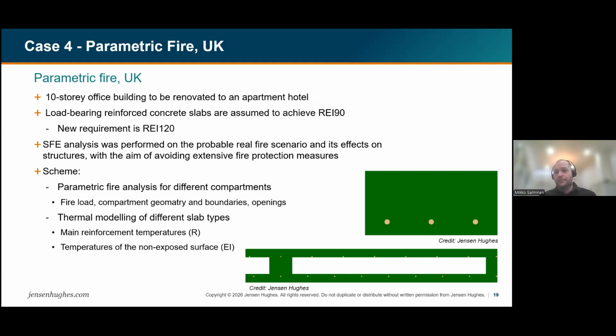And parametric fire works really well in small compartments where you can assume that the temperature distribution is more or less uniform in the compartment. It doesn't really work well if you have a fully open office area, because then you may have a traveling fire moving all around in the floor. But in small compartments, like in this case, the parametric fire curve gives a relatively good estimate for the temperatures in a realistic fire scenario.